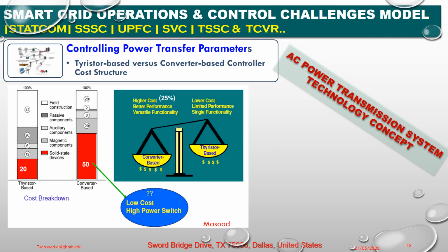Okay, now this is the cost factor. This is a very important slide again. Thyristor based versus converter based controller cost structure. So we are going to give you a breakdown here. On the left hand side, 20% is the solid state devices, magnetic 12%, auxiliary component 6%, passive component 20%, and field construction 42%. So the SVC, as we mentioned, has a large footprint and field construction requires 42% of the cost.